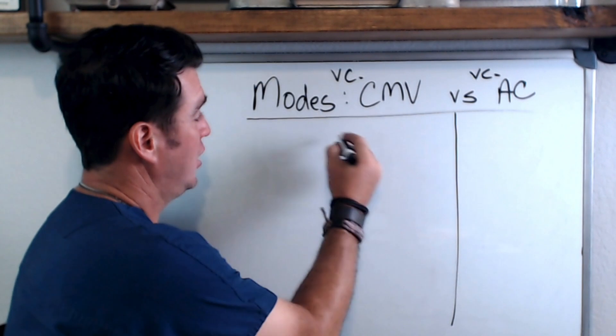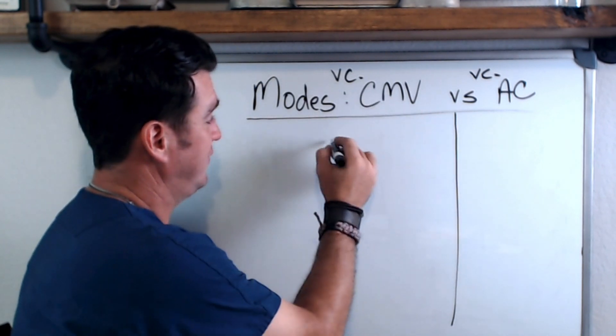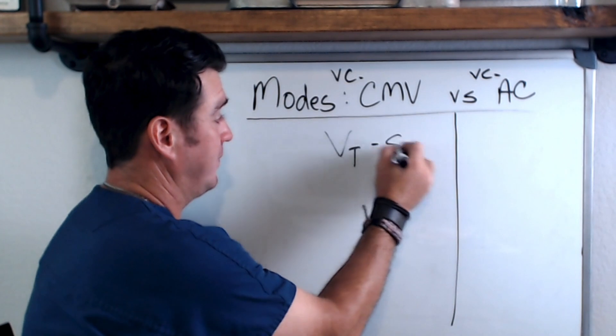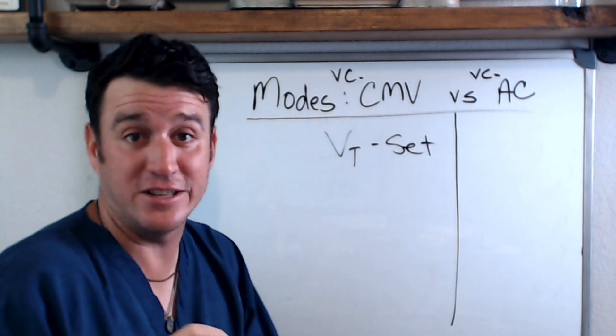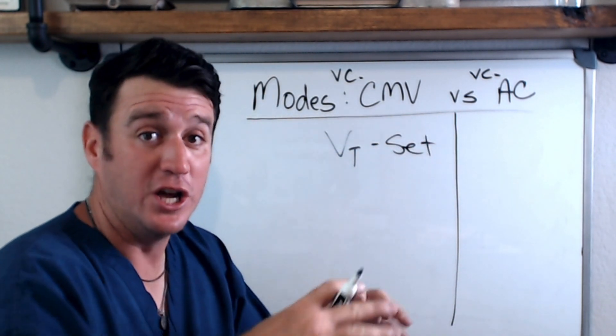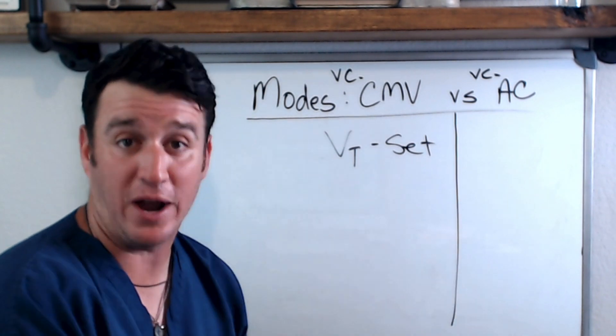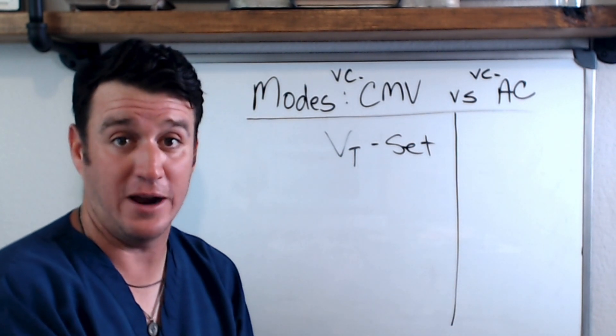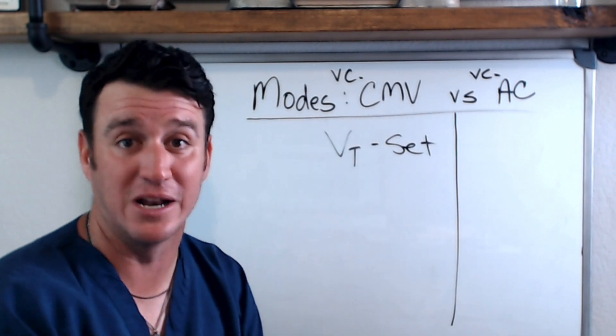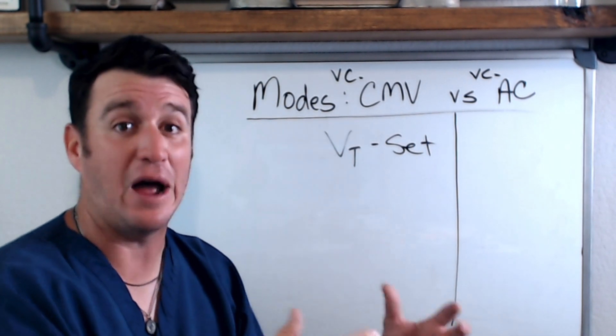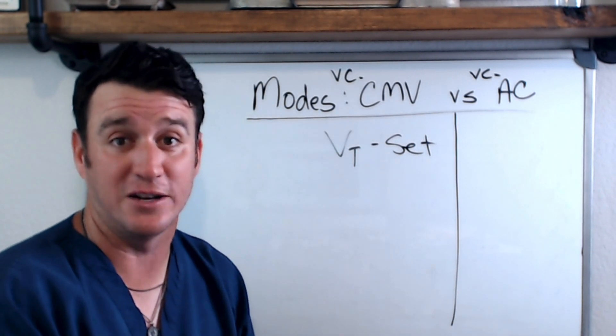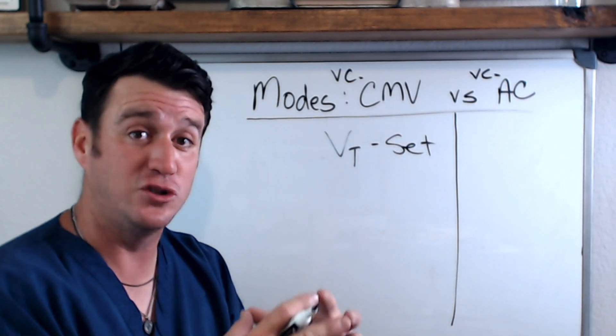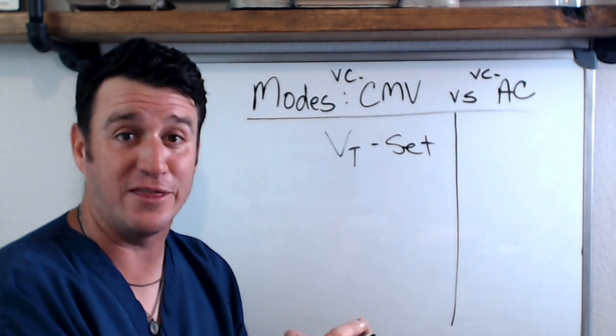So what do we set in volume control CMV? We're going to set a tidal volume — we tell the ventilator how big to make each breath. We'll set 450 milliliters, 500 milliliters, 400 milliliters, whatever it is. That tidal volume is going to be controlled by the ventilator.